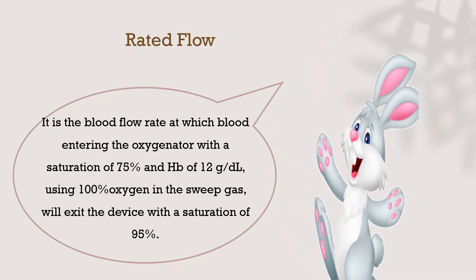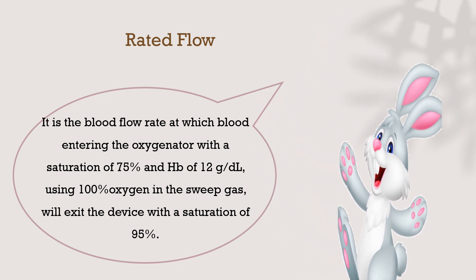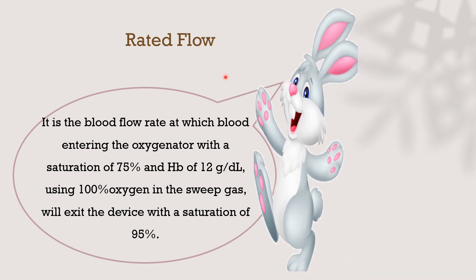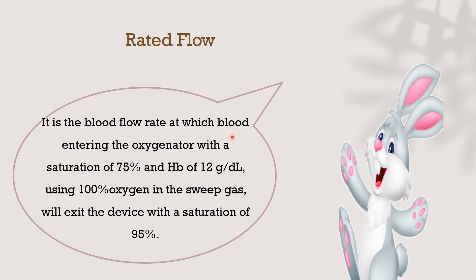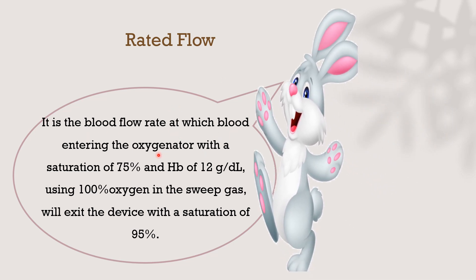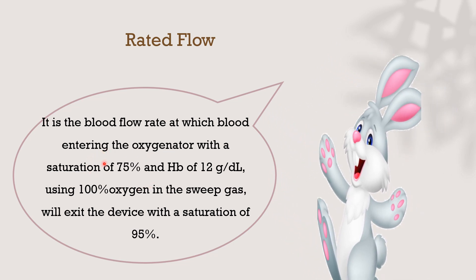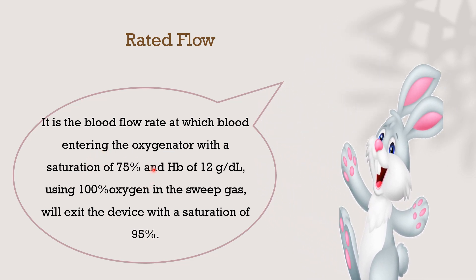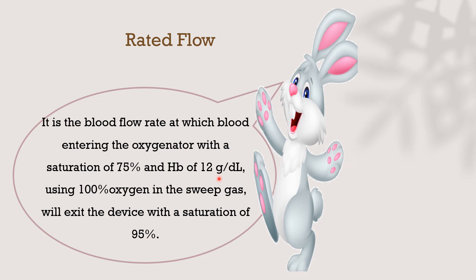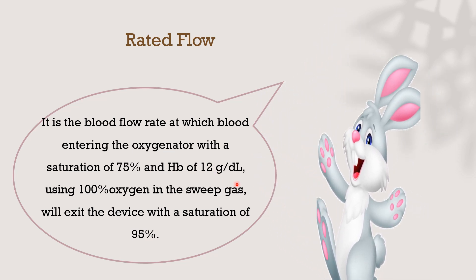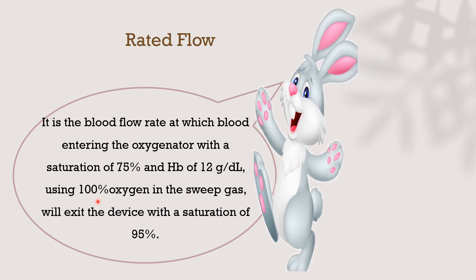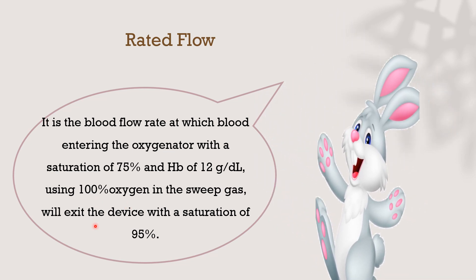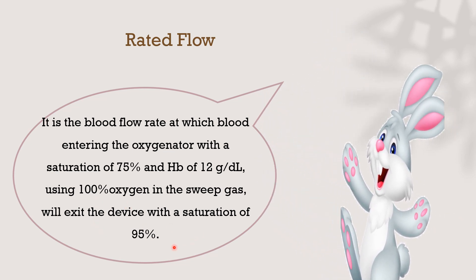Through troubleshooting hypoxia, we need to define some terms. The first term is rated flow. Rated flow is written by the manufacturer on each type of oxygenator and it is the blood flow rate at which blood enters the oxygenator with a saturation of 75%, a hemoglobin concentration of 12 g/dL, and we are giving 100% oxygen in the sweep gas. So the blood will exit the device with a saturation of 95%.